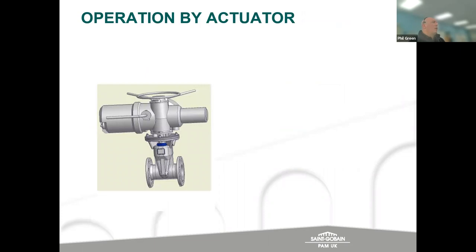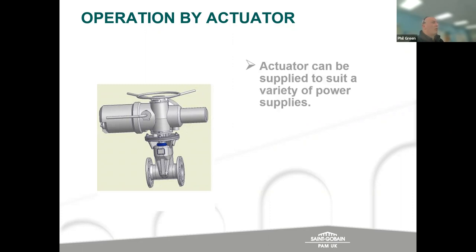When you talk about actuators, this is a device which is usually powered by electricity, but can be pneumatic or hydraulic. It allows remote opening and closing of valves. These can be programmed, or they can be managed from a control center. In this case, the actuator is mounted directly onto a valve, and they are used to operate large diameter valves for which manual operation is inappropriate. And it's obviously important to size the actuator according to the maximum differential pressure that you get in that system.